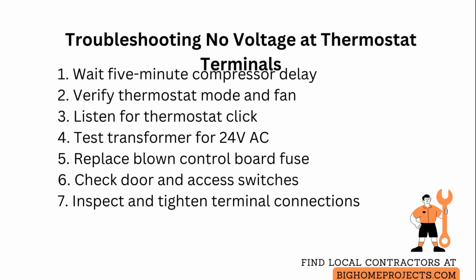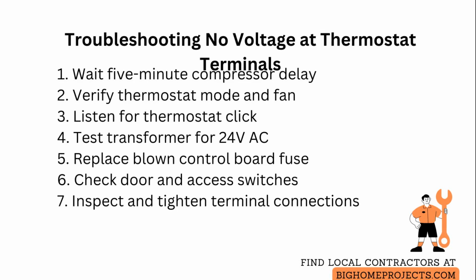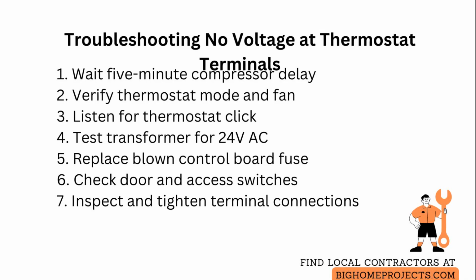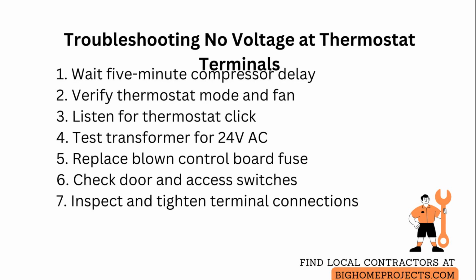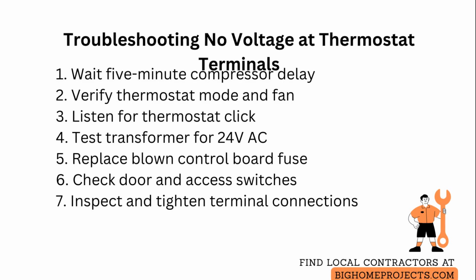Verify the thermostat is actually calling the correct system mode and fan setting by listening for an audible click at the thermostat when changing modes. If no click is heard, inspect the thermostat faceplate and batteries or internal power supply, because a failed display can mislead you into thinking the unit is active.